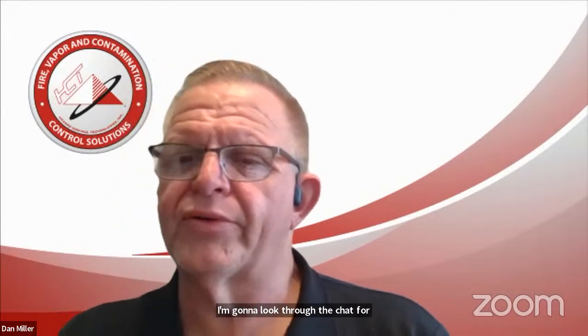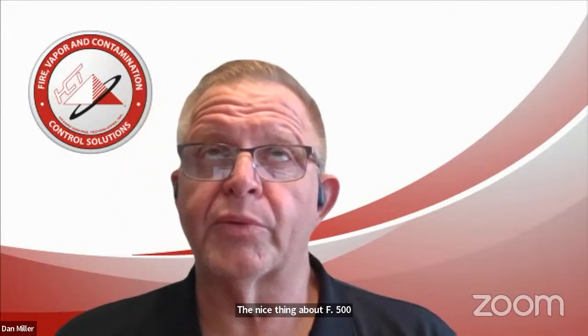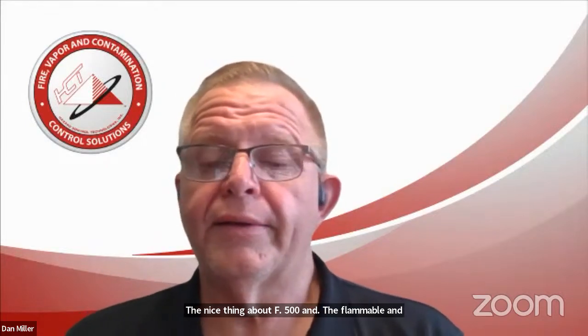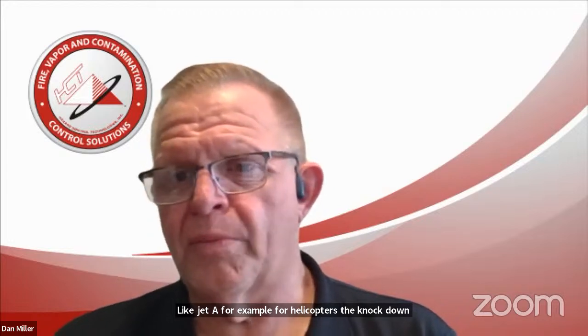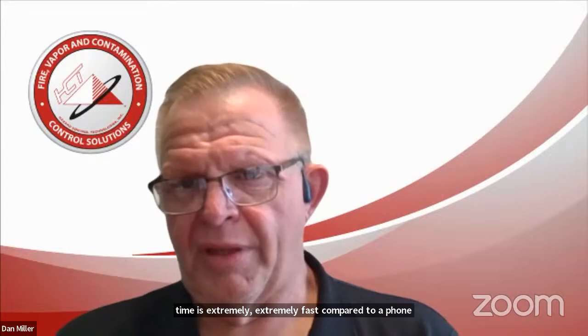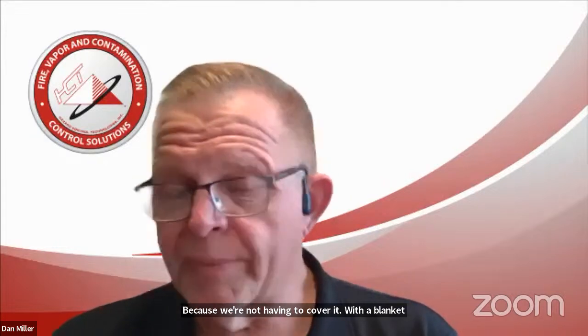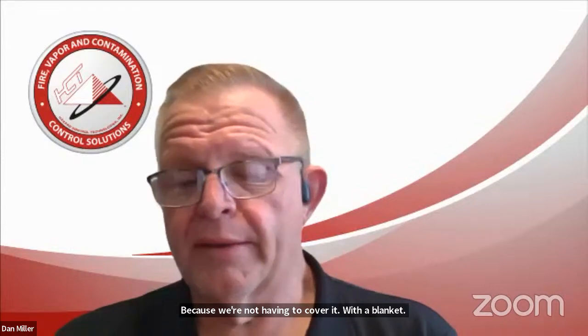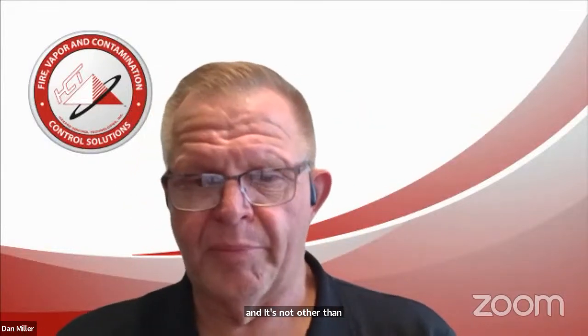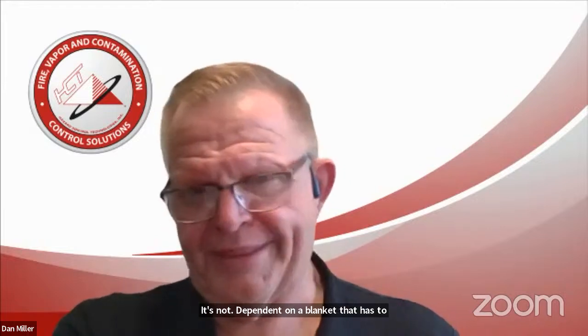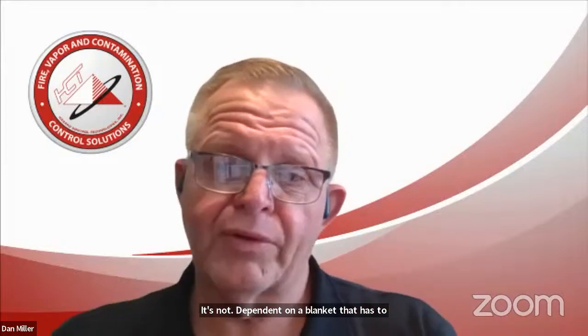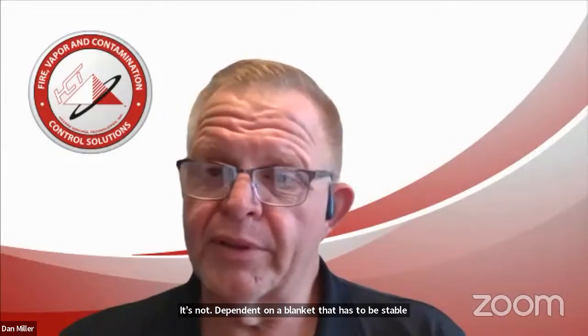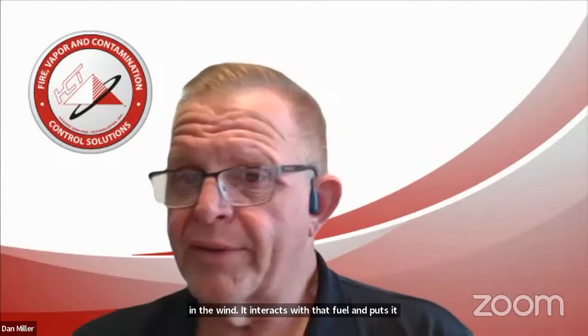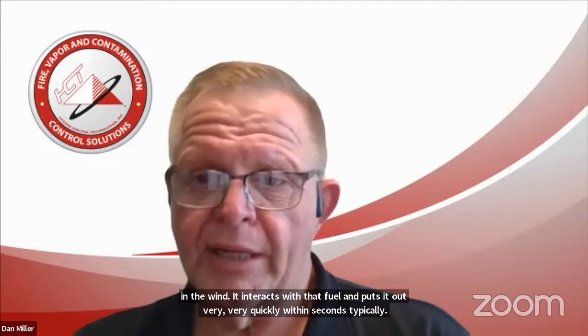The nice thing about F500 for flammable and combustible liquids like Jet A, for helicopters, is the knockdown time is extremely fast compared to foam, because we're not having to cover it with a blanket. It can be very windy on top of buildings, and other than the stream hitting it, it's not dependent on a blanket that has to be stable in the wind. It interacts with the fuel and puts it out very quickly, typically within seconds, with a sweeping pattern. So it works very effectively in those situations.